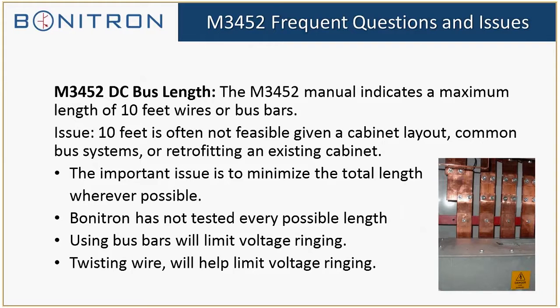So there are ways to limit that sort of voltage ringing. Using bus bars will help instead of using wiring. Some drive manufacturers, in their common bus manuals, recommend twisting the DC bus links. Before you do that, I recommend consulting your drive manufacturer's literature or calling their helpline to see what their recommendations are. Typically it's about 2 twists per foot if you can. However, once you get to the higher current ratings, it's almost impossible to do that. Okay.